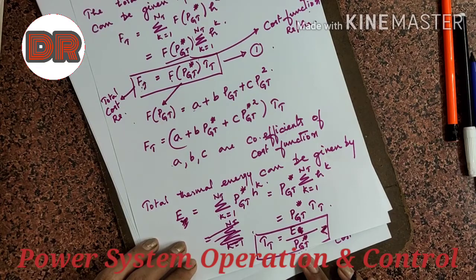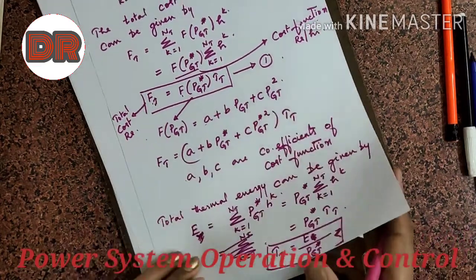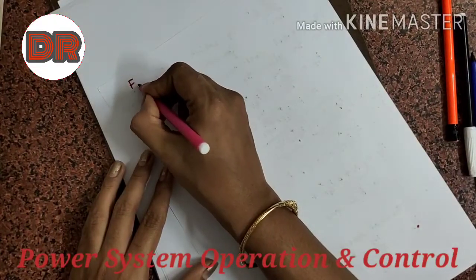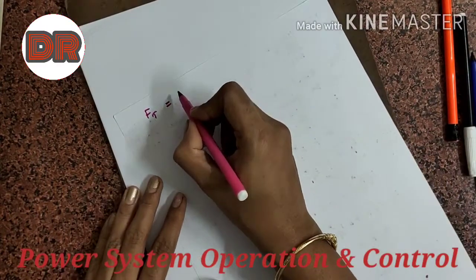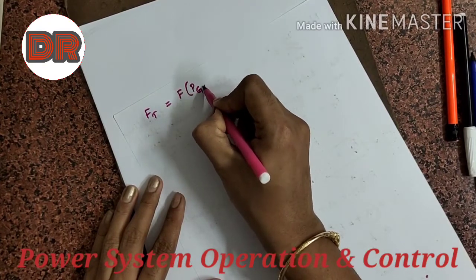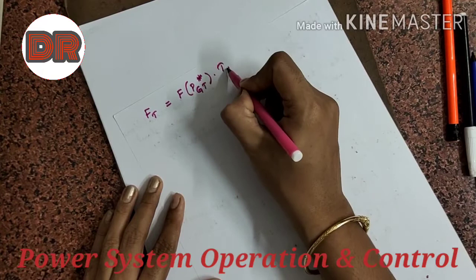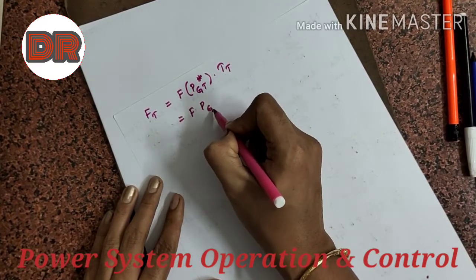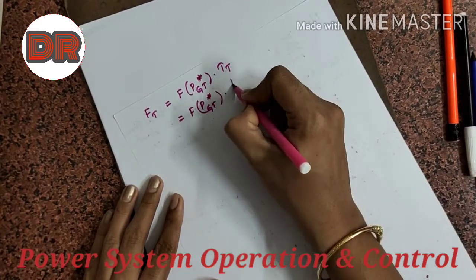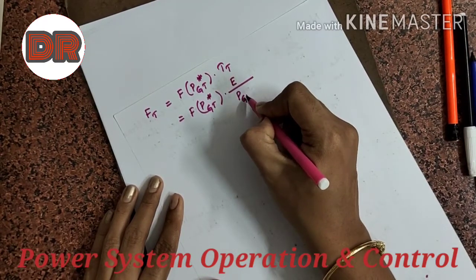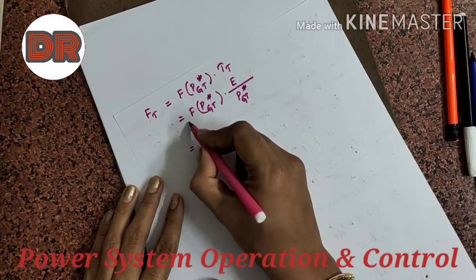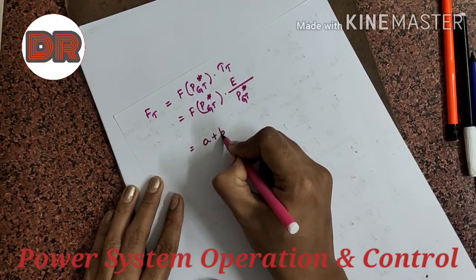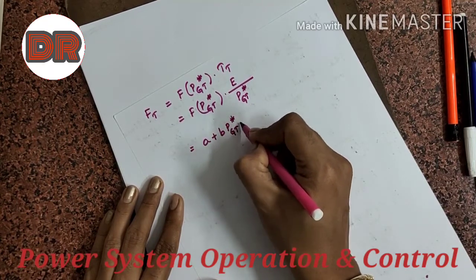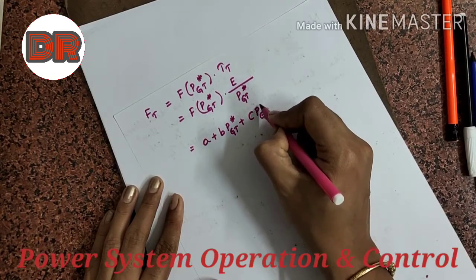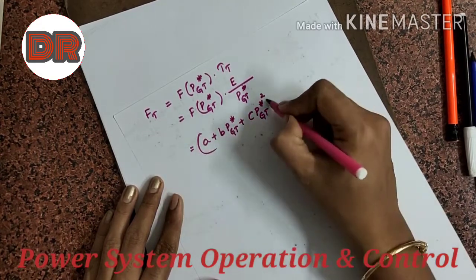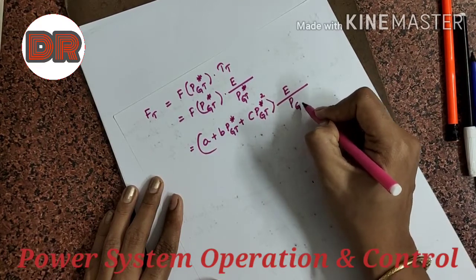Now what is FT? Let me substitute it in this equation. Total cost FT will be given by the function of PGT star into TT, where TT is E by PGT star, and we have written the cost function as A plus B PGT star plus C PGT star square, into E by PGT star.